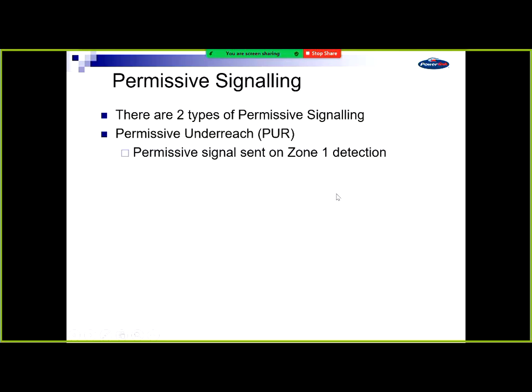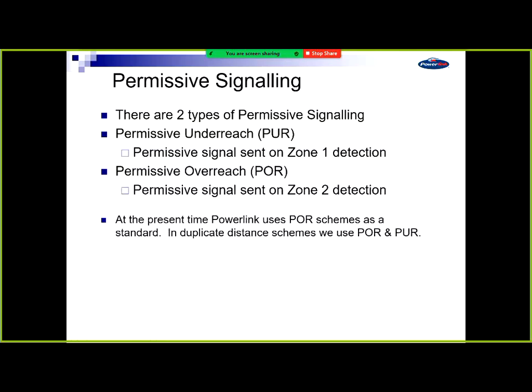So there's two types of permissive, an underreach and an overreach. We tend to use overreach. What the difference is, a permissive underreach gets sent on zone 1, so it doesn't get sent for all faults on the feeder. For that to work, you must have overlapping zone 1s from both ends. If you don't, the zone 2 seen from both ends, a fault in the middle of the feeder will go in slow zone 2. If you've got a permissive overreach, you see all faults on the feeder, but you also see faults beyond the feeder, so you send the signal there. But if your remote end relay doesn't see it in zone 2, it doesn't do anything. So that doesn't really matter.